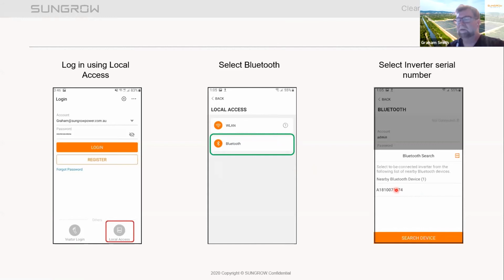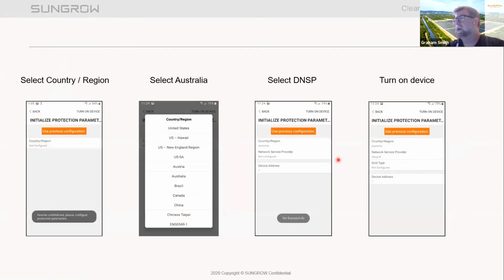Now this is only showing one, but if you have like 4 inverters, you'll see 4 of them listed. You can only do one at a time, so you just need to tap one at a time. So you just tap that serial number there, and you will get this initialization screen. Now this is universal for the entire range that we do. So if you're doing one of the hybrid inverters, the 3-phase ones, you'll go through the same sequence. So you'll get this initialization screen, and you see here it says inverter uninitialized, please configure.